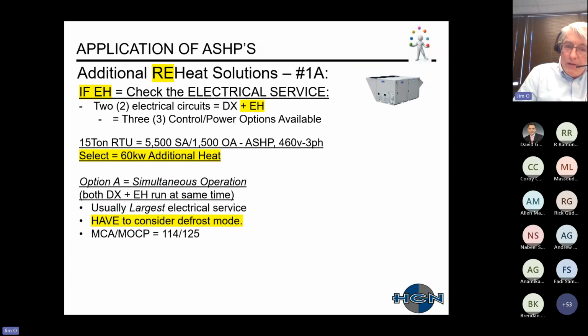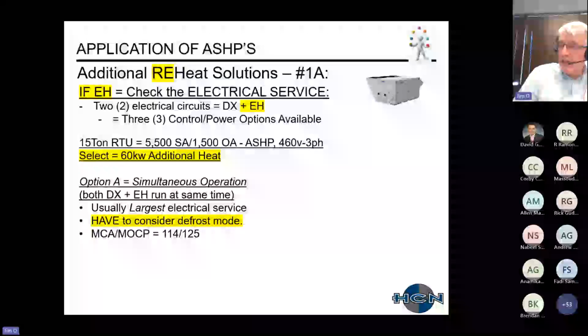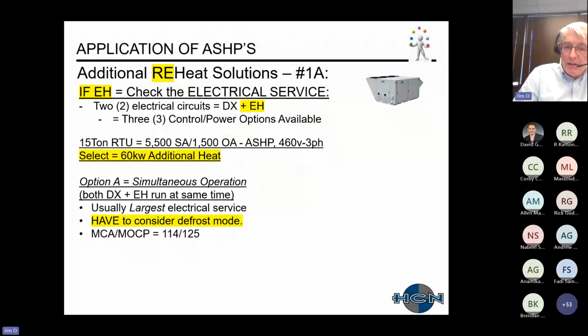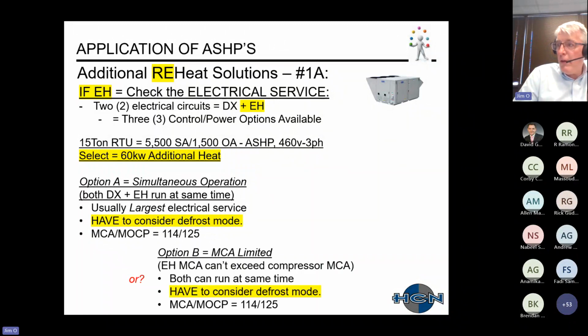Option A is simultaneous operation. This is when you allow your refrigeration system and your electric heater to operate at the same time. This usually results in your largest electrical service. You do have to consider defrost mode.